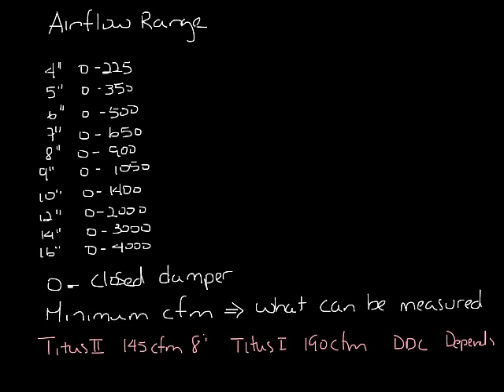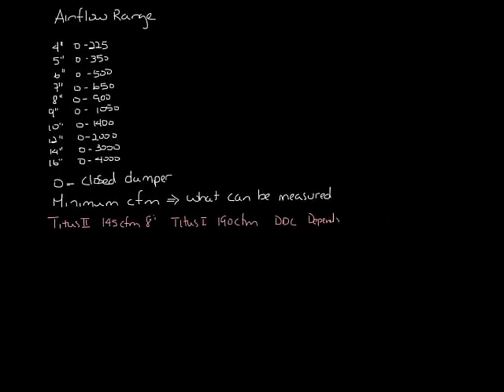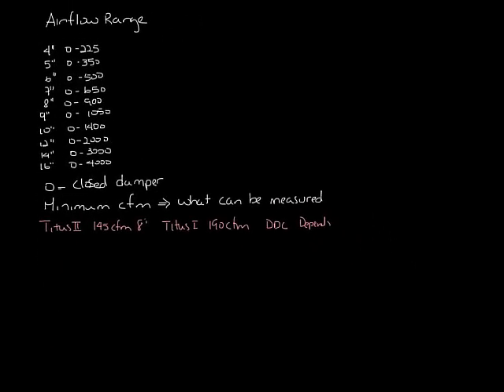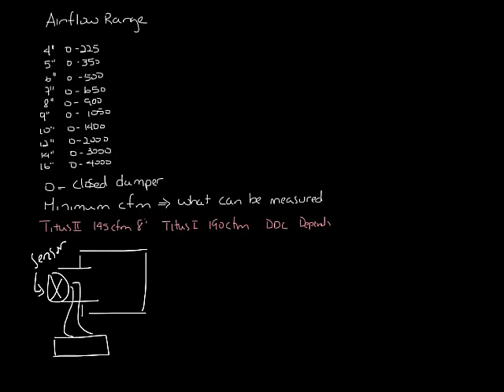Okay, so how is this determined? If you remember in the very first podcast, I talked about the flow sensor in the VAV box being connected to the controller. Let me scoot this out of the way some. It's actually connected to pressure ports on a pressure transducer in the controller. So let me draw a VAV box real quick. There's the unit casing, inlet, and then your flow sensor's in here. Okay. One side is connected to the total pressure side of the flow sensor, and the other side is connected to the static pressure side.